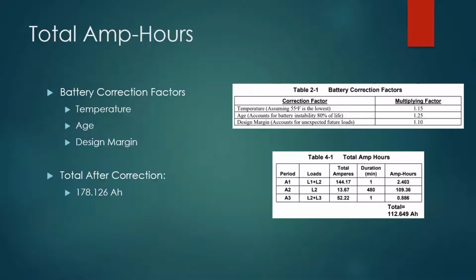For our total amp hour calculation, we had to take into consideration 3 different battery correction factors of temperature, age, and design margin. These were decided to be 15%, 25%, and 10% respectively. Our total amp hours after those correction factors came out to be 178.126 amp hours.